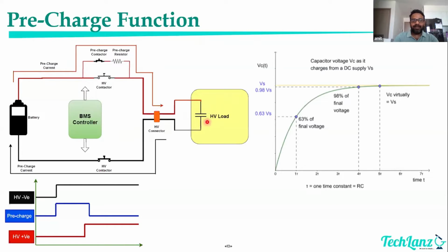As you can see, there is a capacitor, which will be present in almost all electronic loads. These capacitors are called DC link capacitors or CX capacitors. So what happens during HV when we turn on power to the loads? Imagine this capacitor is in a discharged condition. The moment we connect the HV positive and HV negative contactor, there will be a sudden inrush current flowing through this capacitor, because we know how capacitors behave. When a capacitor is discharged, it generally conducts a lot of current when you apply voltage across it, acting like a short circuit for a small period of time. To protect our contactors from getting welded during HV turn-on, we do something called pre-charge.